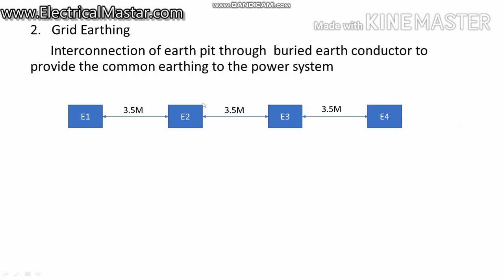The purpose of grid earthing is that it provides a common ground for our connected equipment. In case any one of the earth pits fails, the remaining earth pits will actively participate to distribute that fault current to the ground. That is the purpose of using grid earthing.